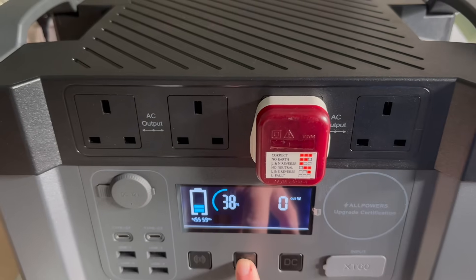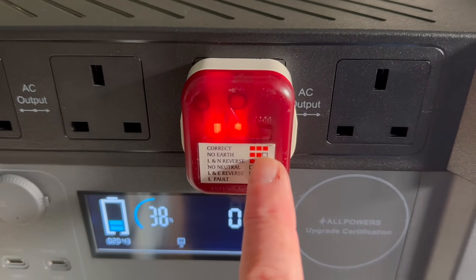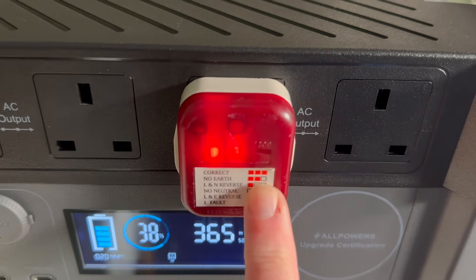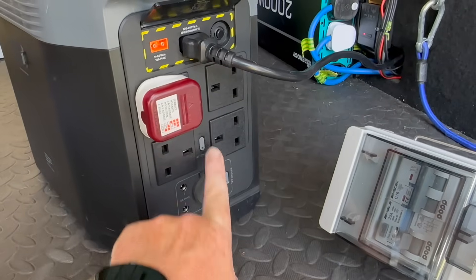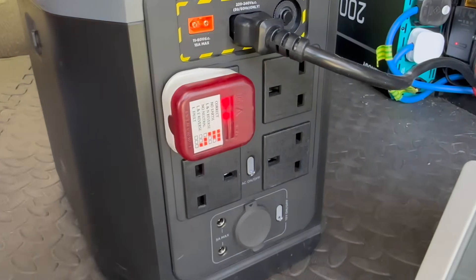I also wanted to test out this built-in protection, RCD, earth bonding and all that in portable power stations. I borrowed one off a friend — an Ecoflow — and I've obviously got the Allpowers. I checked to see whether, if you plug them in on charge — because they've all got fail-over protection, meaning if the mains supply drops out they instantly switch to battery — whether the mains charger's three-pin plug earth is distributed to the three-pin plugs on the unit. It isn't. Power stations don't have earth bonded anything in them.